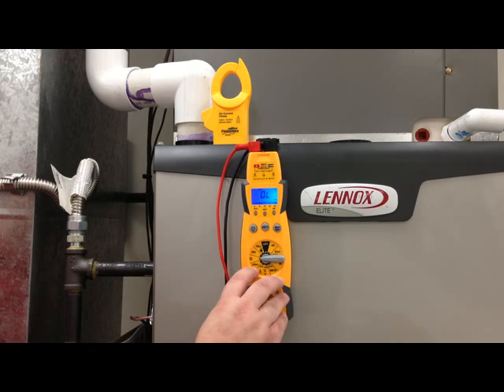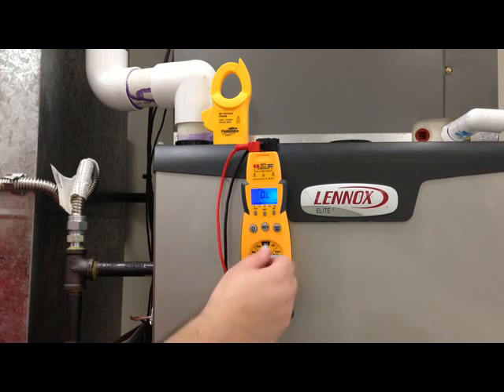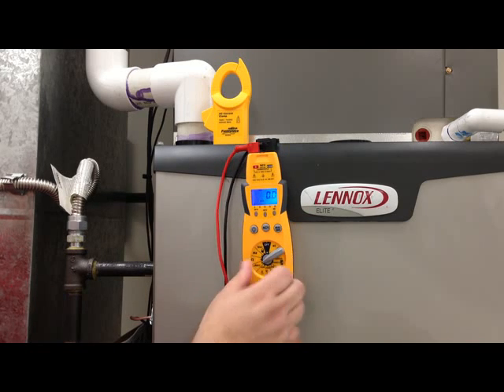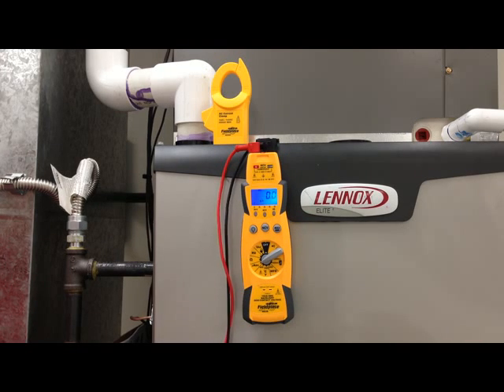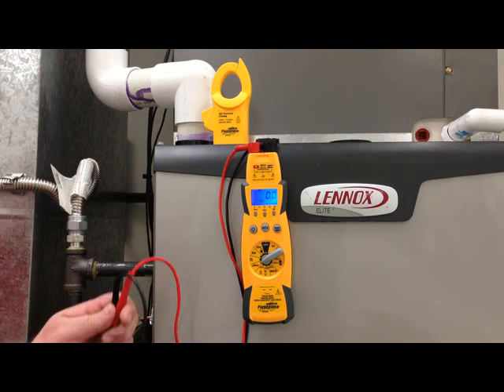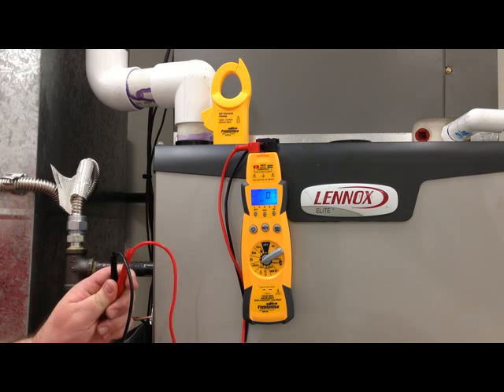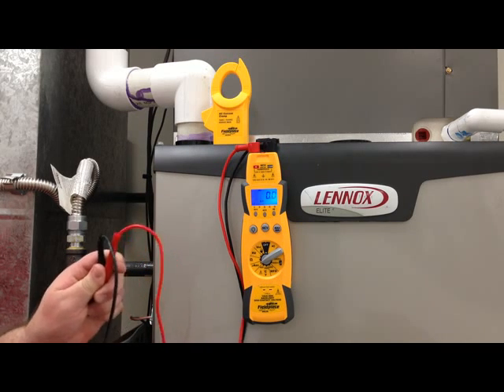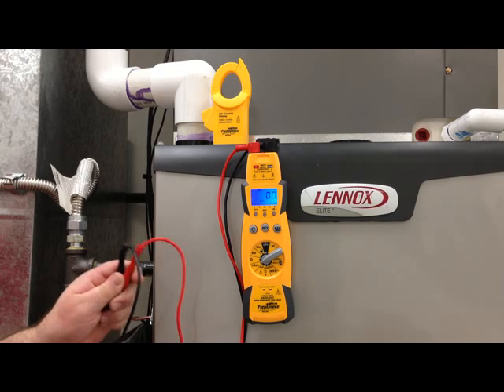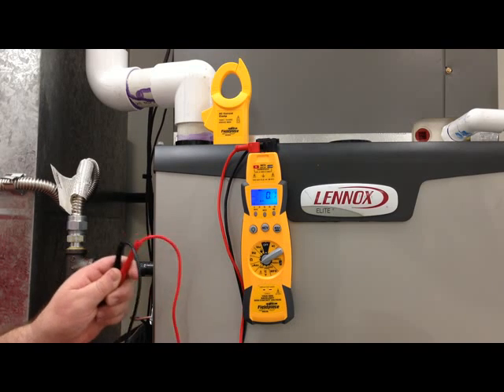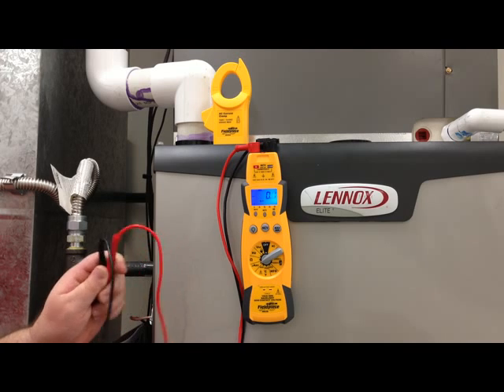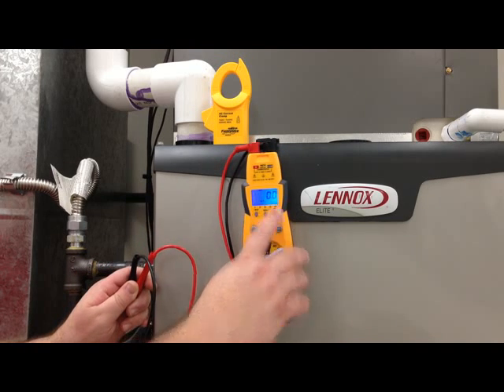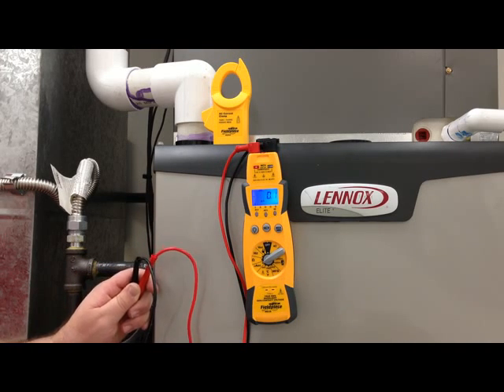Now, right next down here is the little µA DC symbol. This is not milliamps, but this is microamps for checking a flame sensor. To do that, I would set the meter to microamps DC. I would take my meter leads and I would disconnect one wire from the flame sensor and connect it to my meter lead. And I would take the other meter lead and connect it to where the flame sensor wire was connected onto the flame sensing probe. When the burners ignite, I would directly read the flame sensor current on my meter.